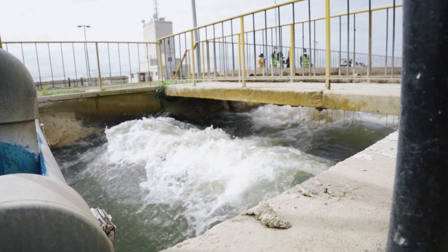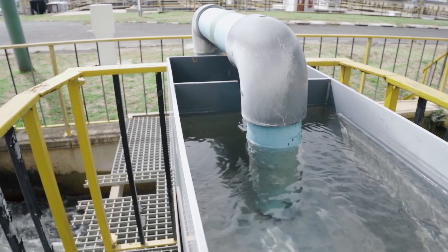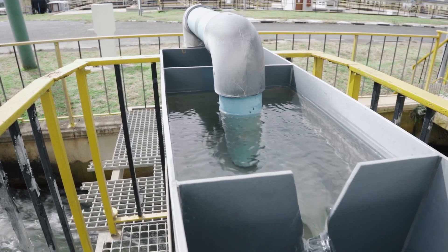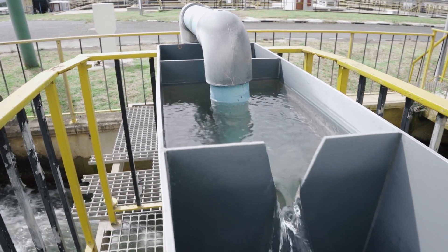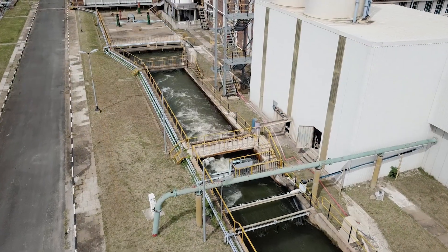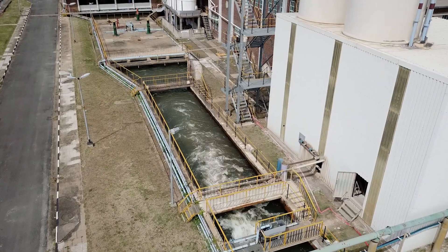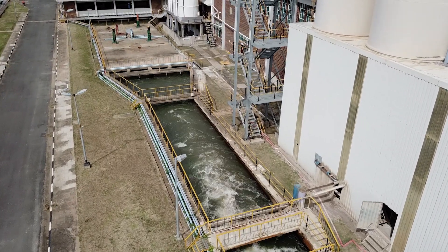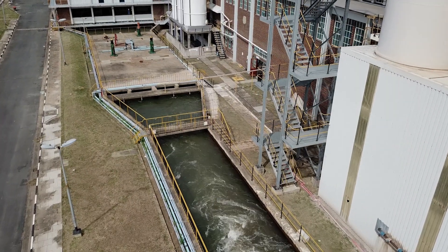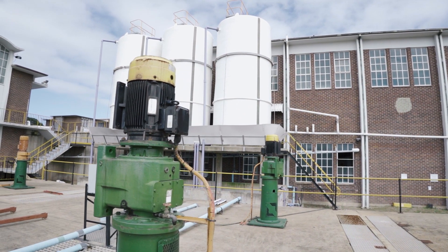The following chemicals are used. Chlorine is used as a disinfecting agent to kill off harmful bacteria and viruses. Polymeric coagulant, generally polyaluminium chloride, helps bring the small dirt particles together to form floc. Lime acts as a stabilizing agent and controls pH levels. Bentonite is added only sometimes to increase turbidity levels for better flocculation.